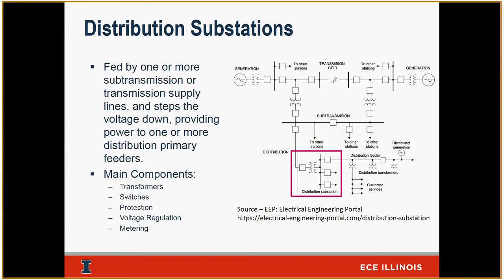These could be either a 34 kV line or a 69 kV line. And they typically are different to provide redundancy. So these two lines will be different. That way, if I lose one, I'm not losing the entire substation. I have a redundant line to serve the rest of the loads. Out of this, I'll probably have a bus with a normal open point. That could be a switch. That could be a breaker. And that ties those two lines together. Typically, they should be the same voltage in here, but I just gave an example of what it would be if we had sub-transmission lines that different.